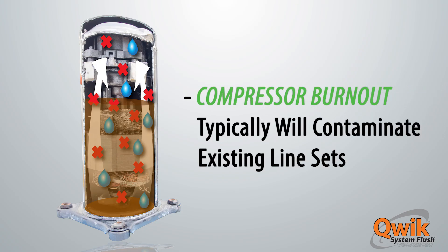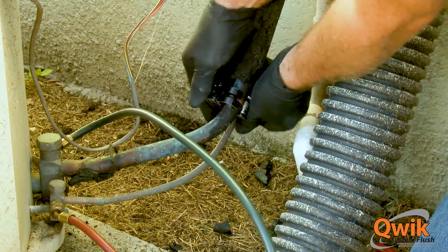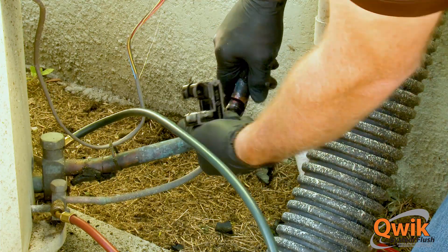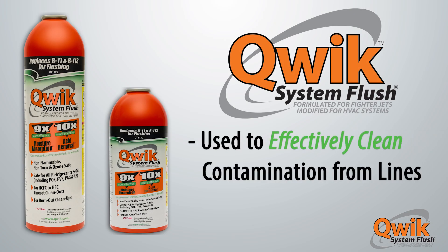After compressor burnout or refrigerant changeout, existing line sets are typically contaminated with residual oil, acid, and moisture. Traditionally, the best way to eliminate these contaminants is to entirely replace the old lines. In cases where this is not cost-effective or even practical, Qwik System Flush can be used to effectively clean existing lines of contamination.